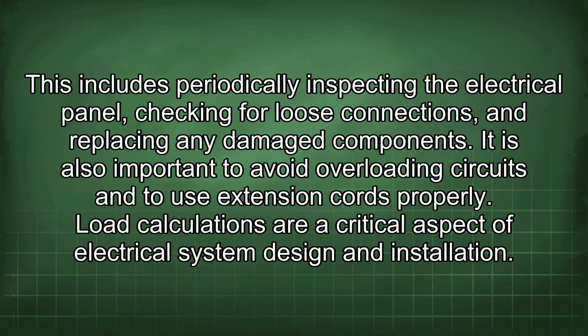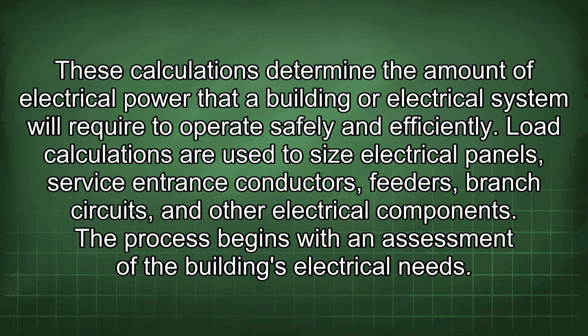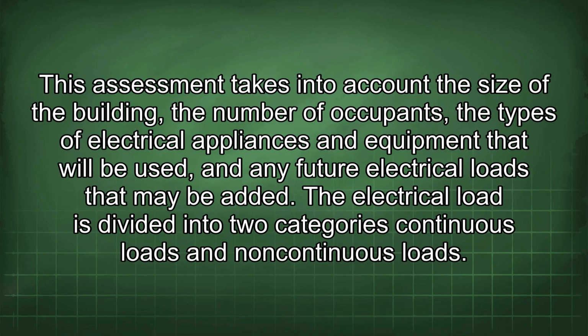Load calculations are a critical aspect of electrical system design and installation. These calculations determine the amount of electrical power that a building or electrical system will require to operate safely and efficiently. Load calculations are used to size electrical panels, service entrance conductors, feeders, branch circuits, and other electrical components. The process begins with an assessment of the building's electrical needs. This assessment takes into account the size of the building, the number of occupants, the types of electrical appliances and equipment that will be used, and any future electrical loads that may be added.